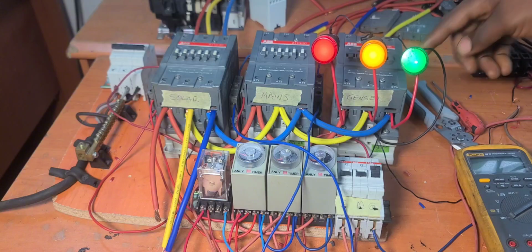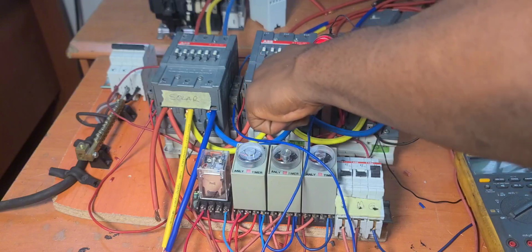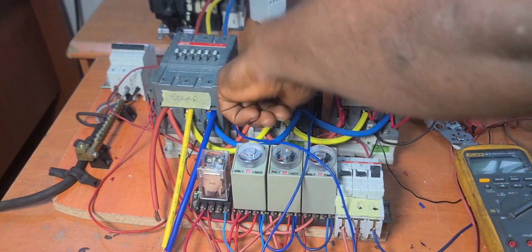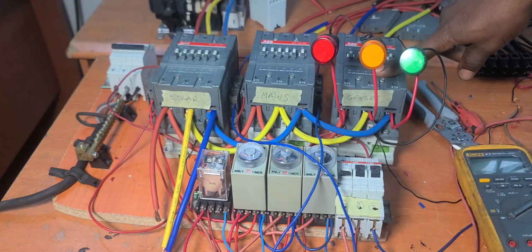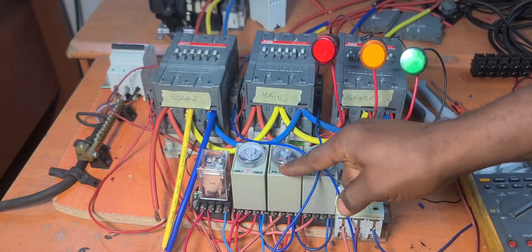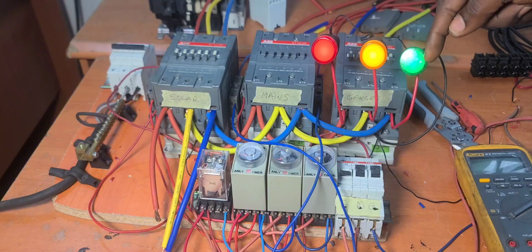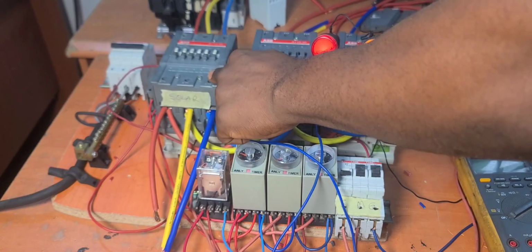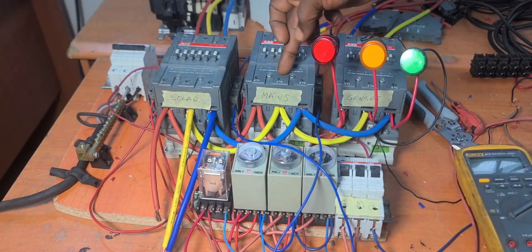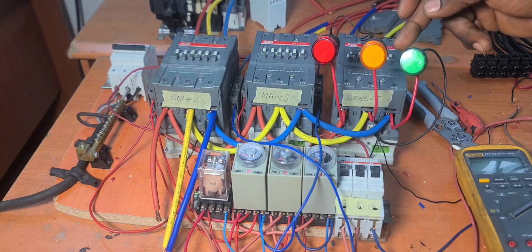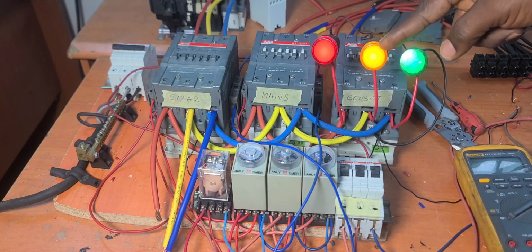All right, so now that this genset is on, if mains is restored, for example, let us restore the mains and see what happens. So this is the mains. You see, it has disconnected this one immediately, and then it's going to delay for some seconds, and then it's going to energize this one, and then we still have power here. All right, so let us activate solar and see. Exactly the same thing. It has disconnected this one, no power on the load, delays for some seconds, and energizes this one, and then we have power on our load.